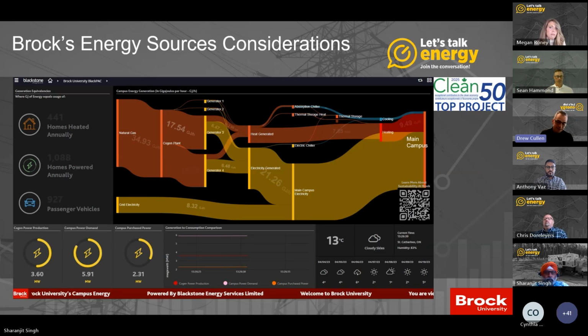As you said about the utility, you better look at your connection agreement and talk to your local distribution company. See what rules and measures they have in place and what's defined in your contract. In our case, we weren't allowed to generate or export to the grid, so we had to test, record, and prove that the battery would shut down within 100 milliseconds of the breaker closing to the utility. Making sure we had the proper equipment and protection relays in place, and that they would respond, was imperative to whether this was going to work.